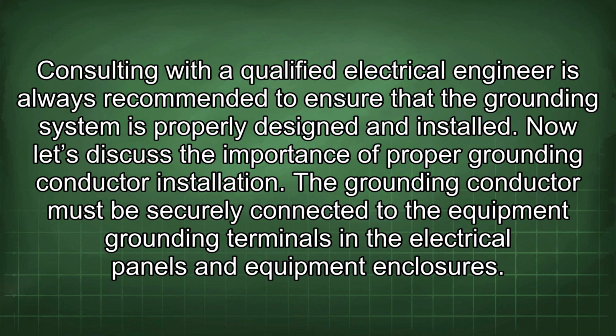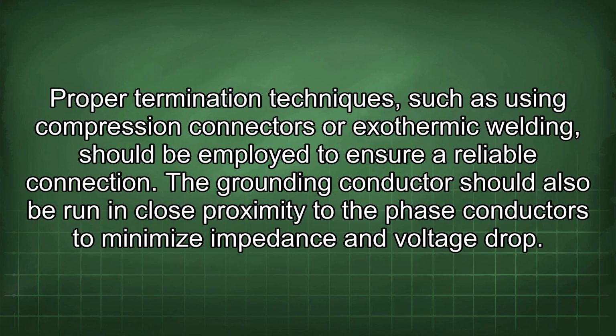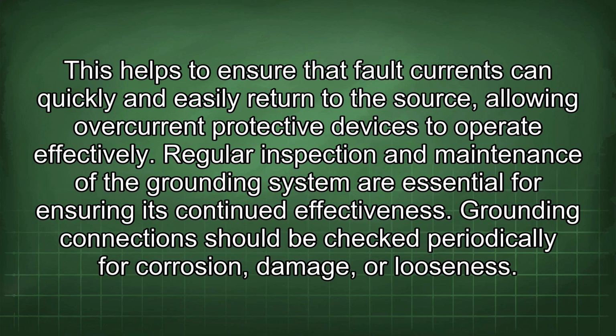Now let's discuss the importance of proper grounding conductor installation. The grounding conductor must be securely connected to the equipment grounding terminals in the electrical panels and equipment enclosures. Proper termination techniques, such as using compression connectors or exothermic welding, should be employed to ensure a reliable connection. The grounding conductor should also be run in close proximity to the phase conductors to minimize impedance and voltage drop.